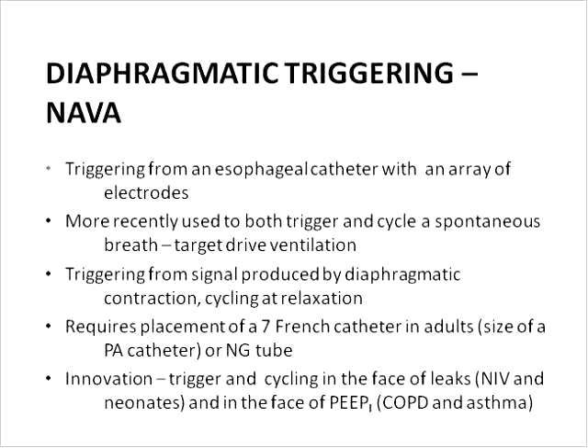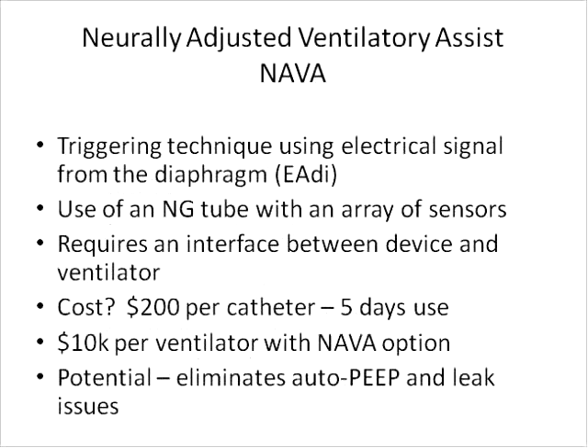And it makes sense to me that diaphragmatic or NAVA would be very useful in patients who have severe intrinsic PEEP that you can't get around. So it uses this technique using the electrical signal of the diaphragm. I'll show you a quick picture. It does require an interface between the device and the ventilator, and at this point only is available on the Maquet ventilators. The catheters are about $200 per patient, and the addition of the module is about $10K per ventilator. But it does have potential.